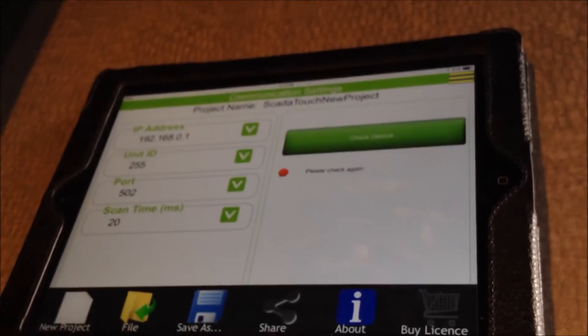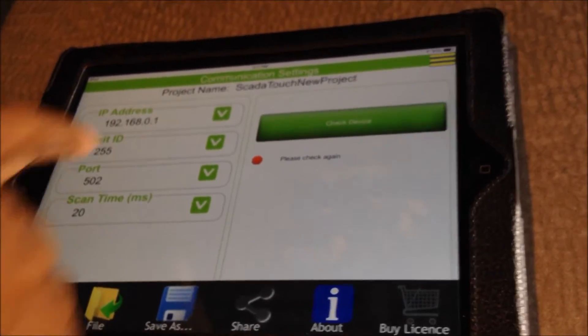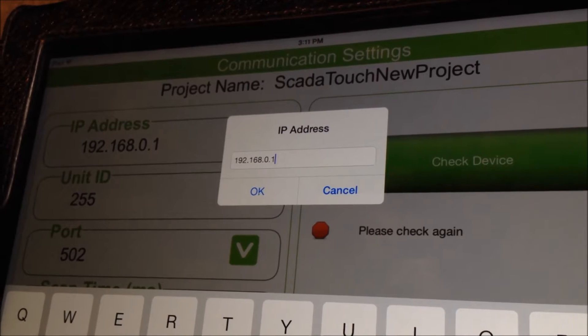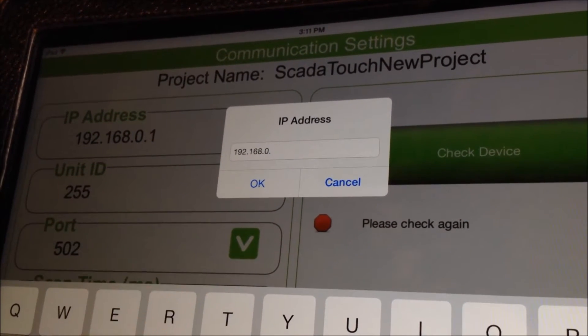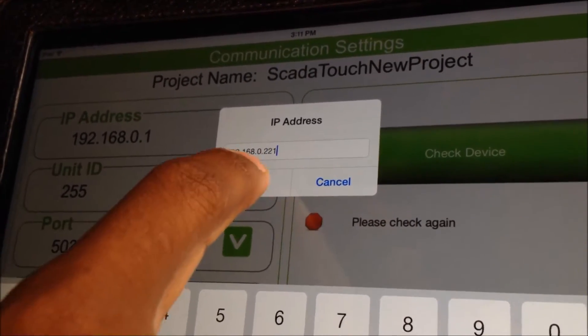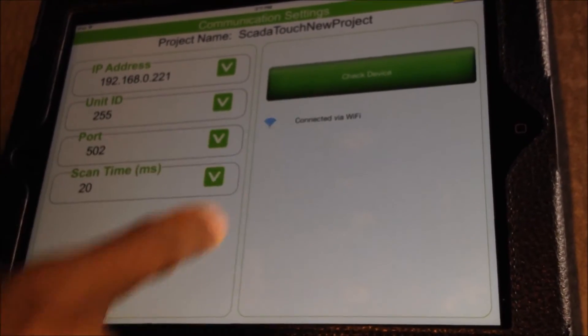Next, once you are in the app, slide from left to right and it will open up the area where you can set up your communication settings. Type in the IP address of the Modicon M221 PLC: 192.168.0.221. Click OK, then click Check Device — you are now connected to the PLC via your router.